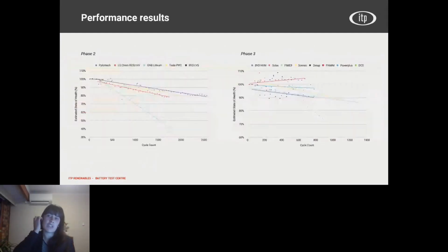So how do we measure the performance? One of the things we look at is capacity retention. One of the ways we do that is by running what we call a capacity test on all the batteries each month and measuring how much energy is discharged.